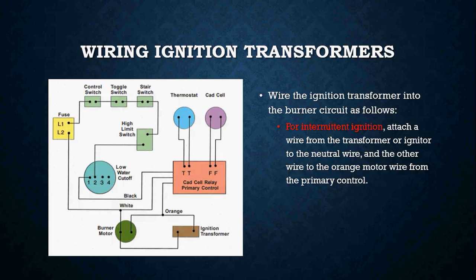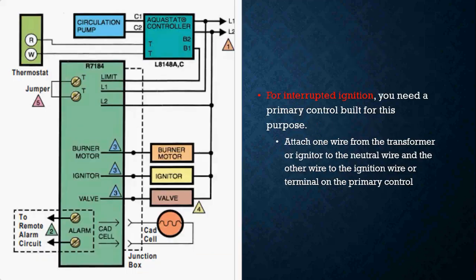When it comes to wiring an ignition transformer, wire the ignition transformer to the burner as follows. If you're doing intermittent ignition, all you're going to do is attach the wire from the transformer or igniter to the neutral wire, and the other wire to the orange motor wire from the primary control. Now this is going to apply if you're using the simple 3-wire Honeywell primary control.